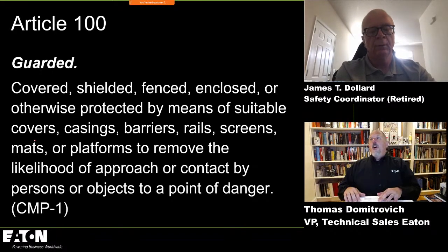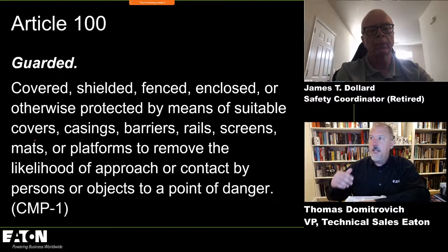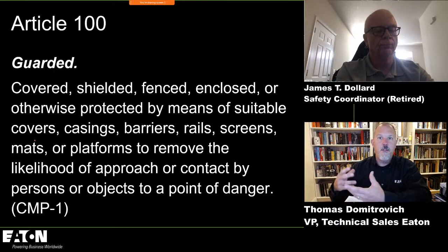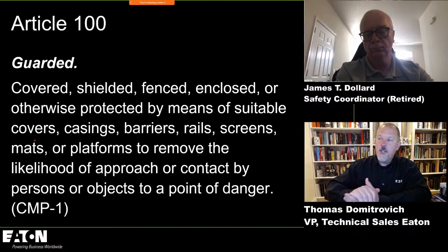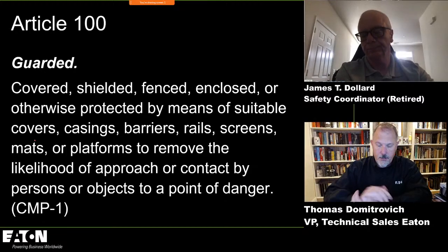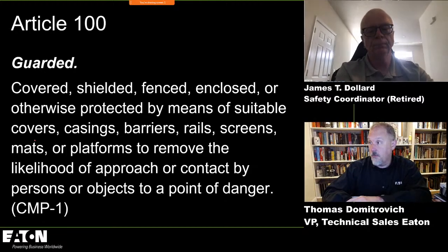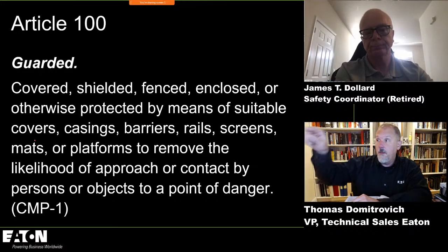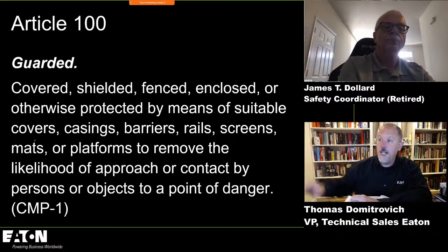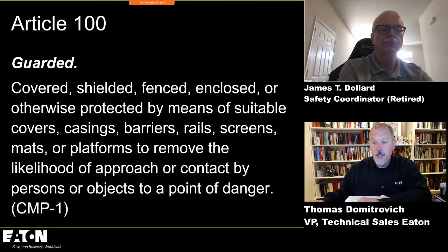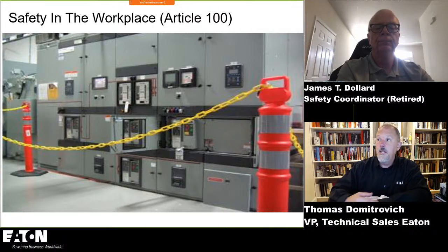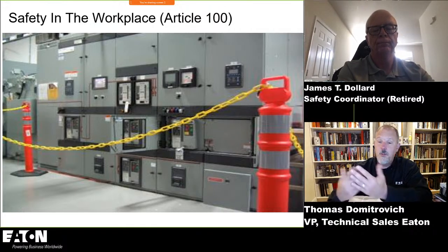Now, when I looked through the code on barriers, I learned very quickly that they use the term barriers in the NEC, but they also use this term guarded a lot. And in many different areas, there's provisions to require guarding of energized parts. So I threw in the definition from Article 100, using the 2020 code as a reference. And again, it says to remove the likelihood of approach or contact by persons or objects to a point of danger. So there are many different areas that would speak to guarding an area.